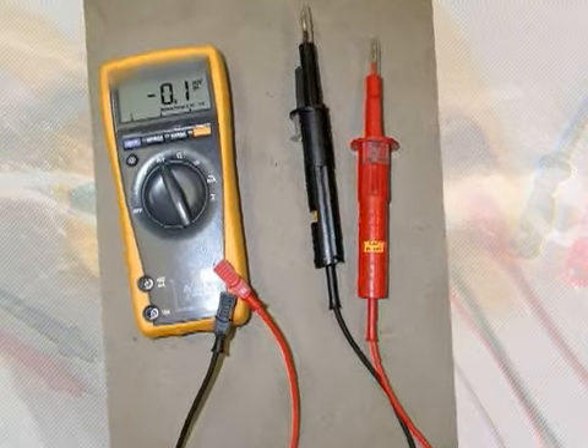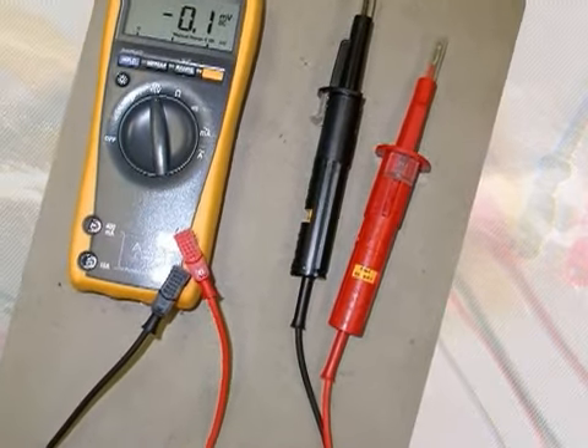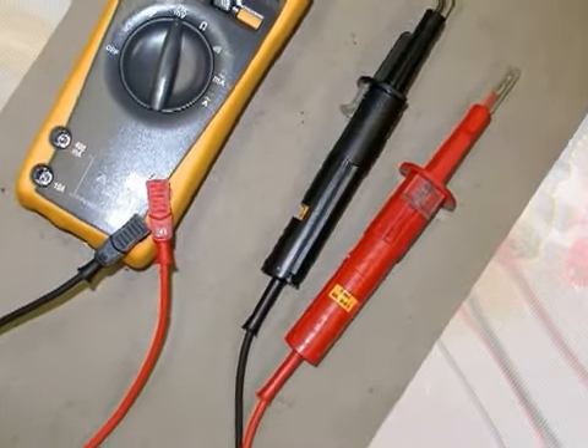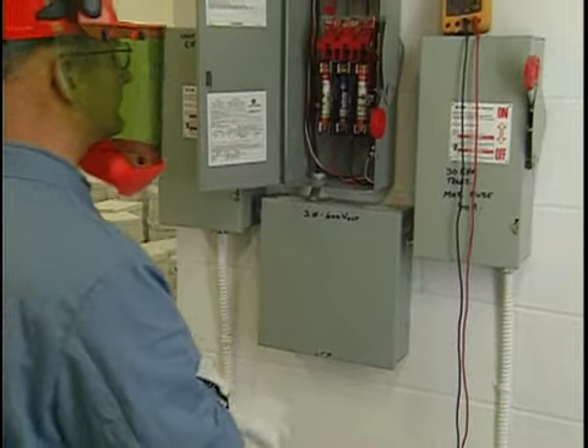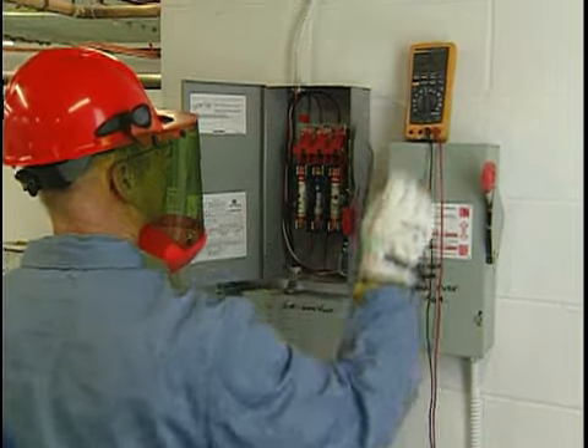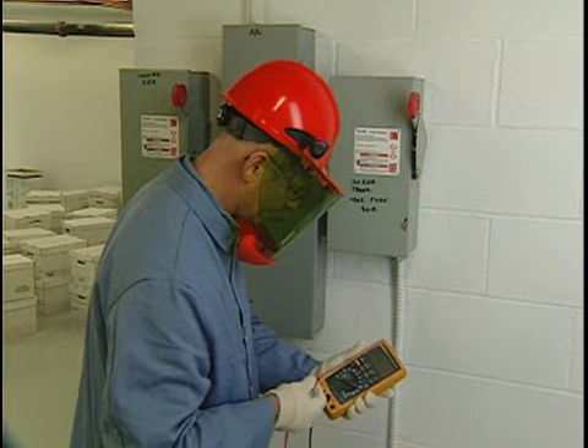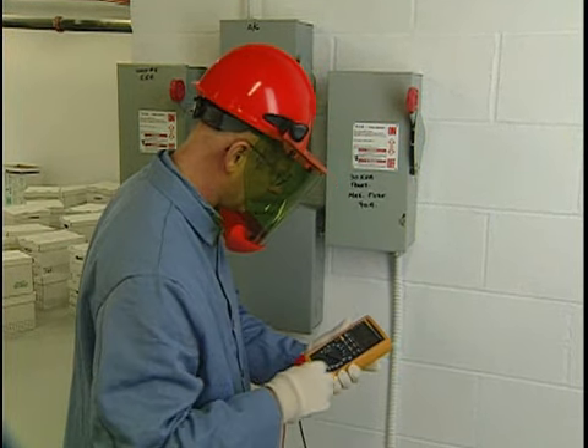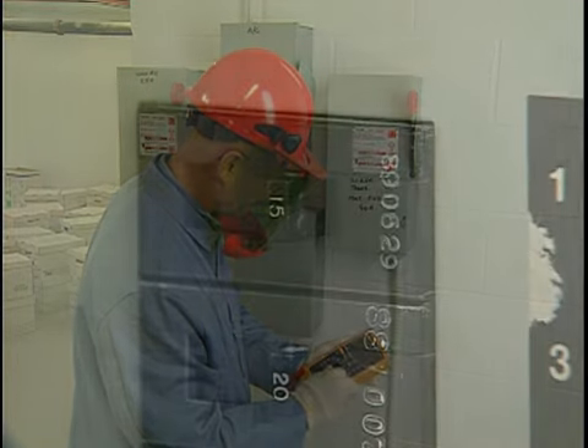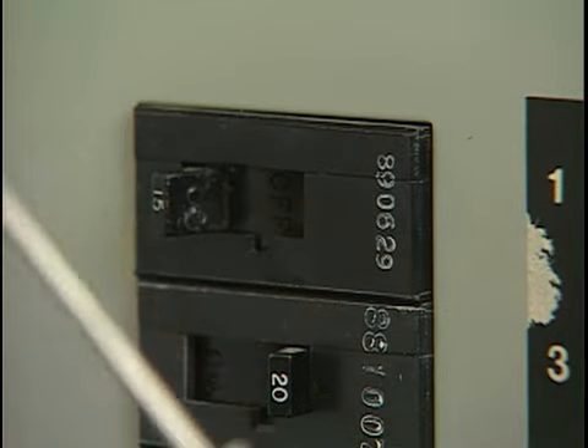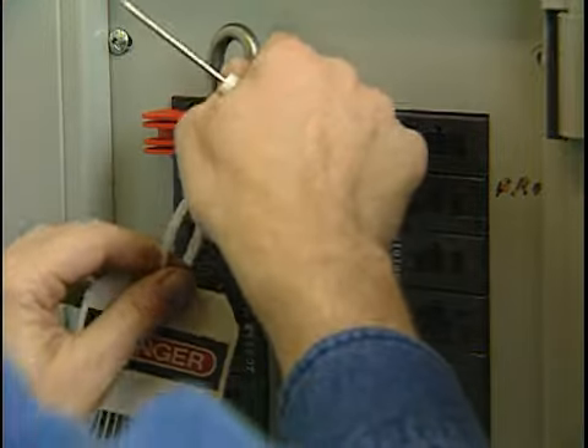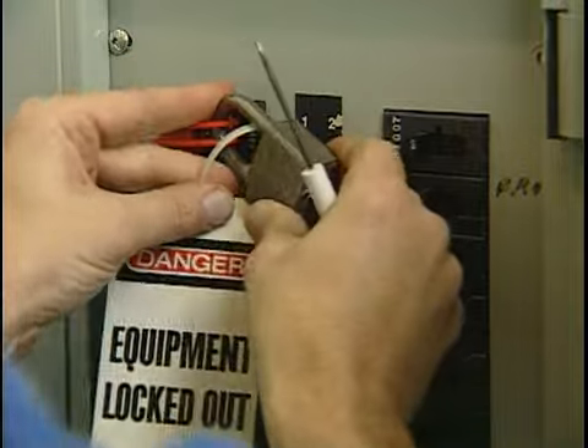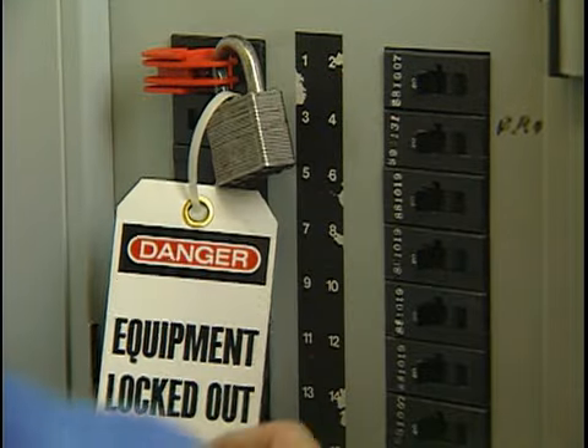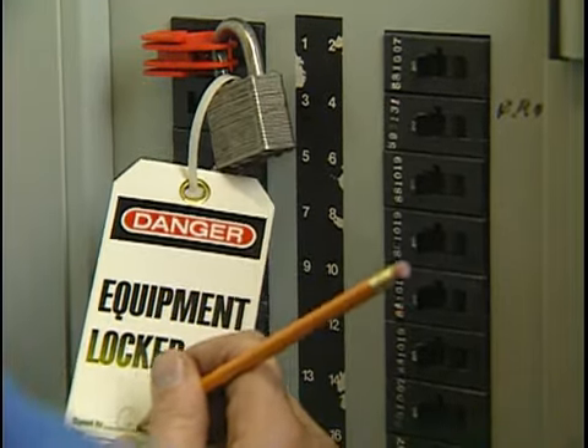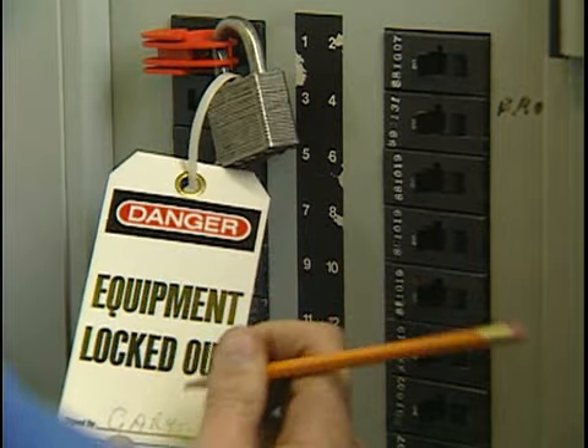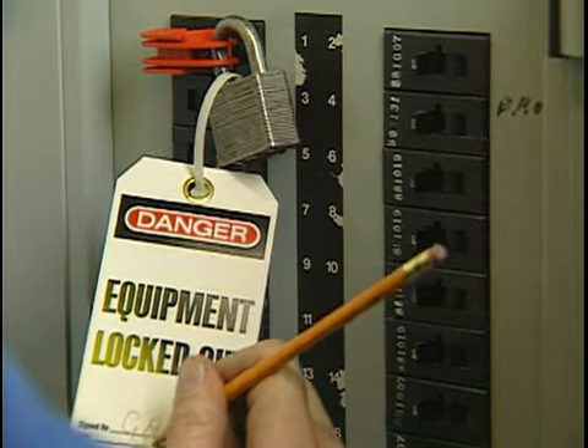Use an approved minimum Cat 3 meter with fused leads as an additional protective measure. Select a multimeter that meets your highest voltage measurement needs. Check that meter leads are connected to the correct terminals and the meter is on the right setting. De-energize the system wherever possible. Lock out and tag out at the panel or switch. Verify that you have de-energized the correct circuit. Lockout, tagout is a key safety component.